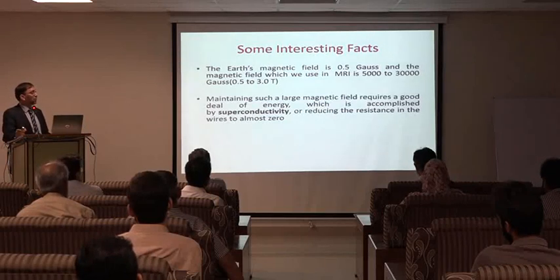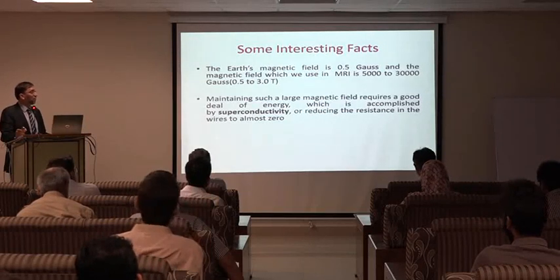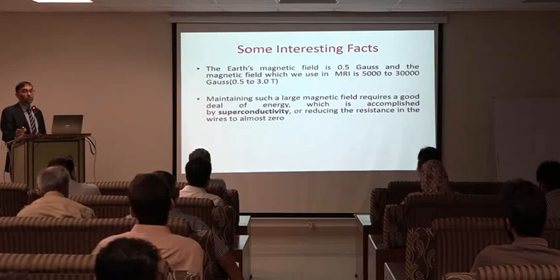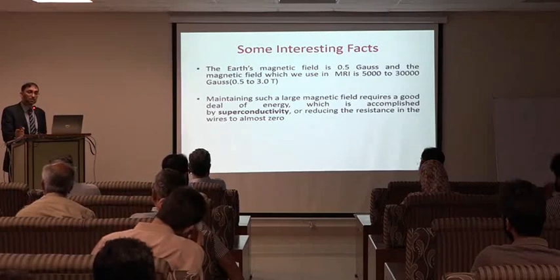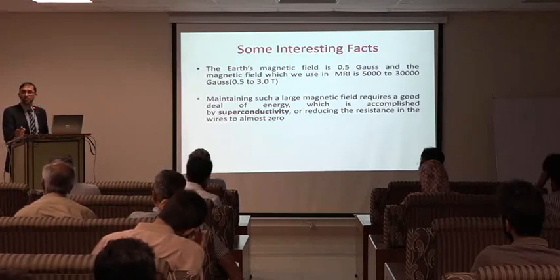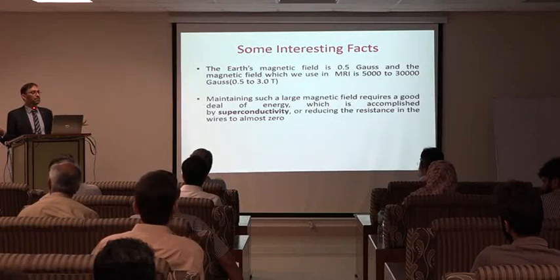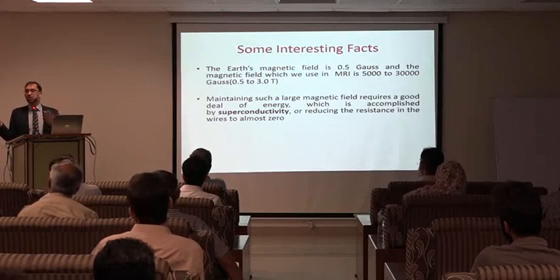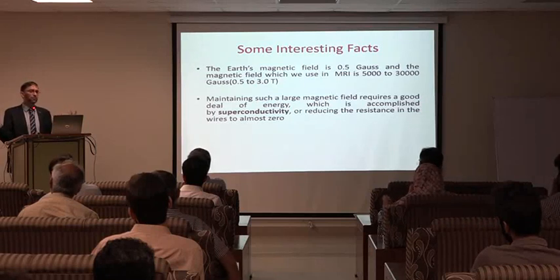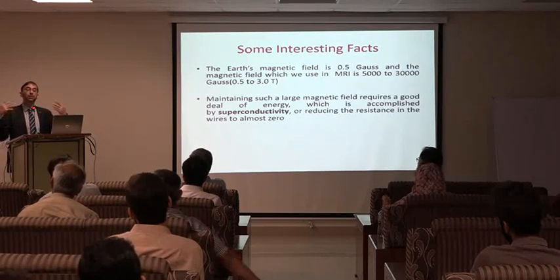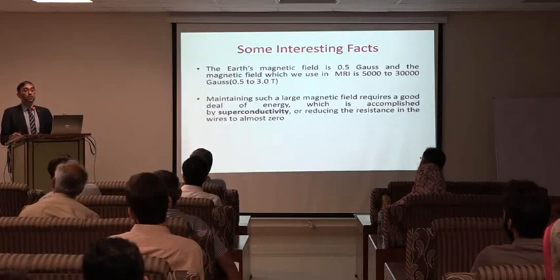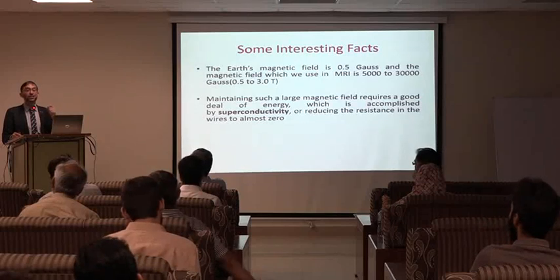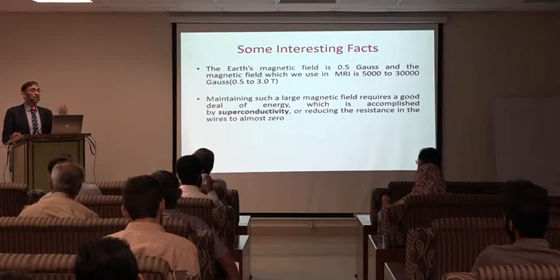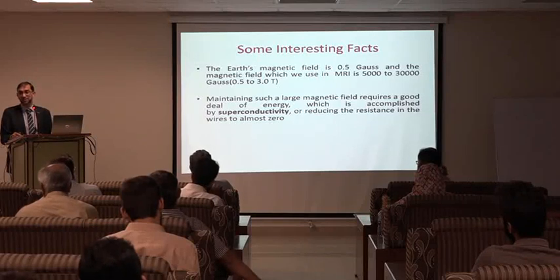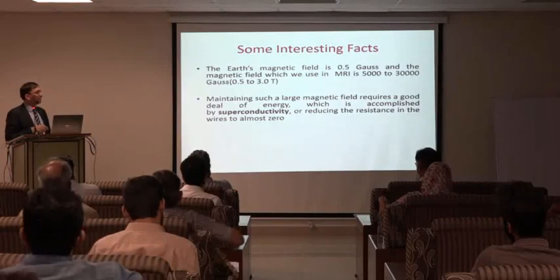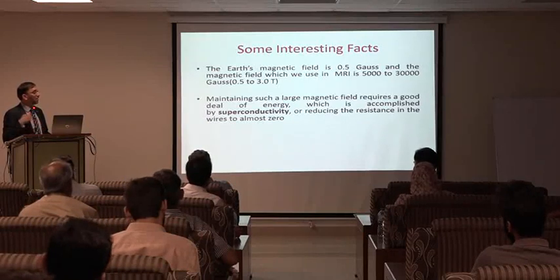Maintaining such a large magnetic field requires a good deal of energy, because either you go with the permanent magnets. Permanent magnets cannot give you that high magnetic field strength. The permanent magnets can give you something around 0.45 Tesla. I said that at Shifa International Hospital, they have got 0.43 Hitachi scanner. That's it, 0.43 Tesla Hitachi MRI scanner, because that's working on the permanent magnet case. However, to produce high magnetic field strengths, you have to use electromagnet. And in electromagnet, you have to give in electrical energy. Only then you'll produce the magnetic field, right? So maintaining such a large magnetic field requires a good deal of energy, which is accomplished by superconductivity.